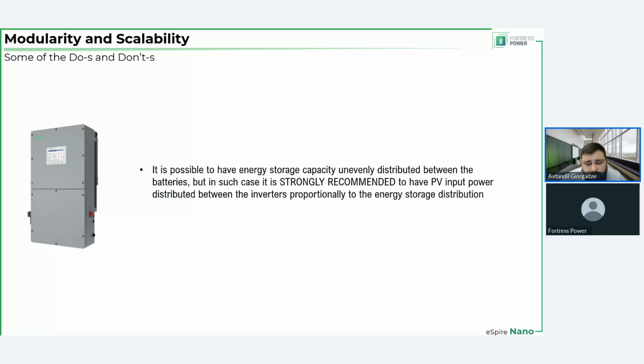the inverter also has to manage the power between the batteries and do its best not to have one depleted quicker than the other, because in that case, you will not only lose some capacity that is not available to you. I mean, if you discharge a battery long enough, that's inevitable anyway. But what's going to happen is that the inverter whose batteries have been depleted will not function. So yes, you lost some of the capacity, but that was expected. But you also lost some, or in this example, half of your power output capability, right?